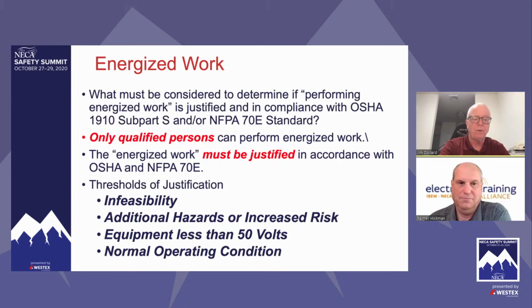Equipment less than 50 volts, normal operating condition was a really good change that came in a couple of cycles back into NFPA 70E. So, there's a number of things that we have to look at. We have to make sure that there's no defects in the equipment. There's no evidence of impending failure. All of the screws and bolts are in. And there's another piece in there. You have to make a determination that the equipment is properly maintained.